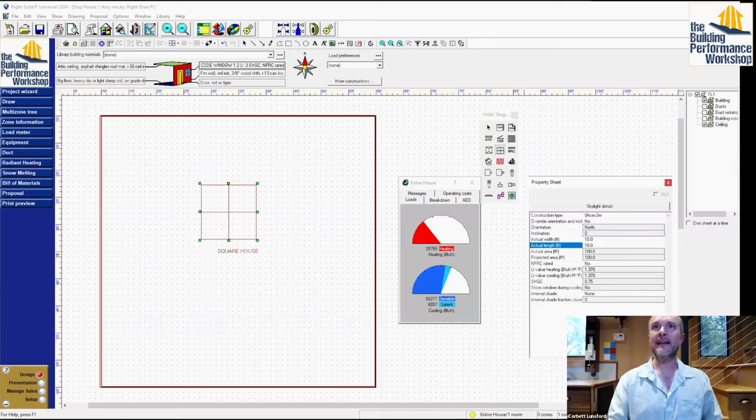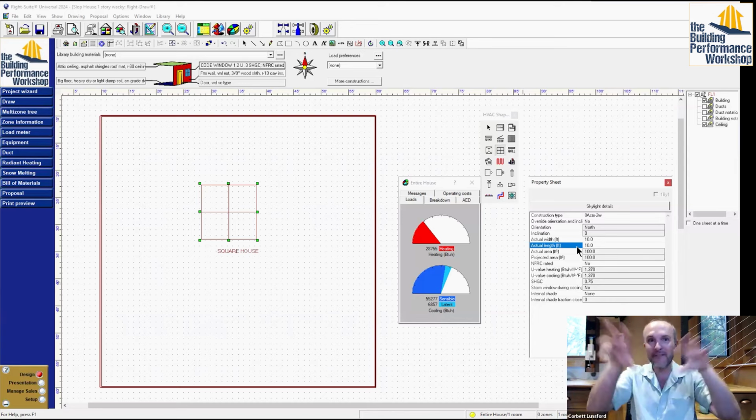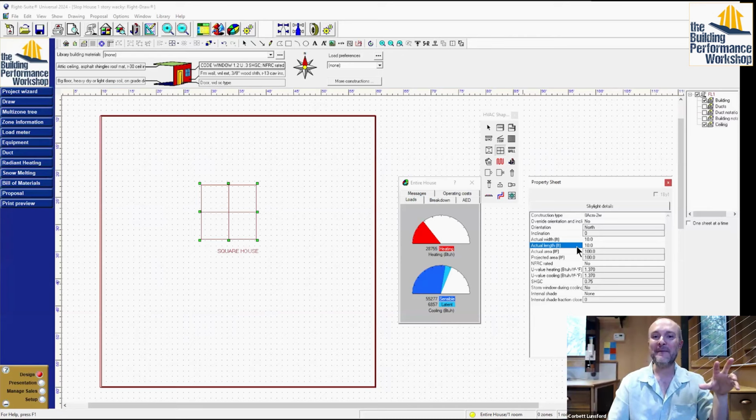Let's make it 10x10. Okay, now right here, we've got 55,000 plus over 6,000. We just cleared that 500 square feet per ton number by adding a 10x10, or however many smaller ones would make it up. And that's a huge number. That's 100 square feet, roughly 4% of your total ceiling area made up of glass, just a single pane of glass with nothing special about it.